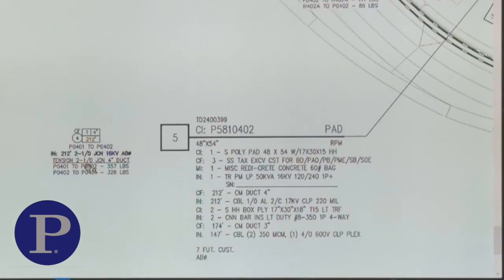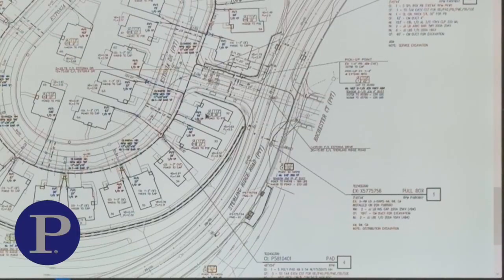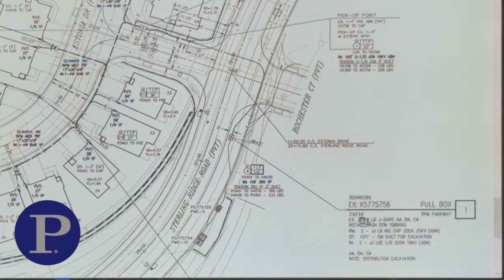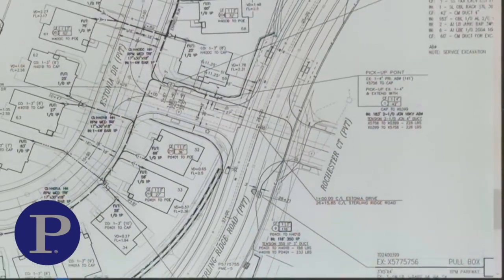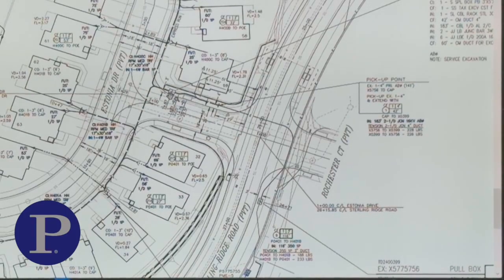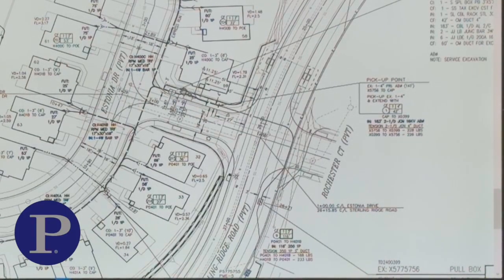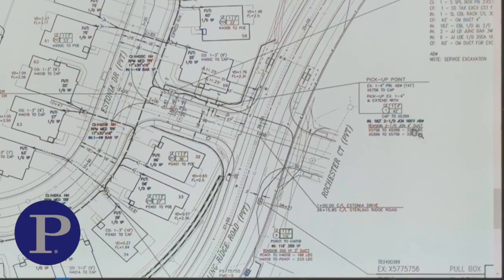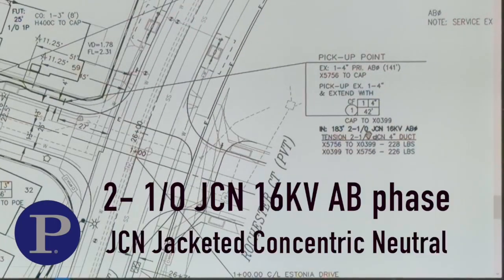Moving back to this plan, so now we know that this call out right here, let me go back to the source here. So we know that my source down here, this existing pull box right in this area right here, is going to feed up into this pull box. So there's going to be a cable call out in between these two structures right here. And here it is, 183 feet, 2-1-aught, so that's 2 conductor 1-aught, jacketed concentric neutral, 16 kV, and we're going with A and B phase.